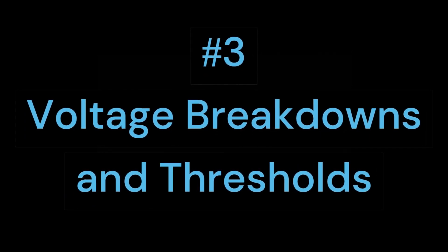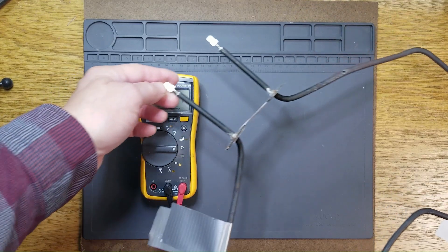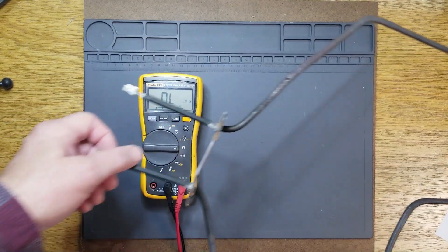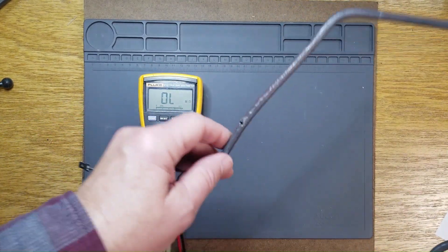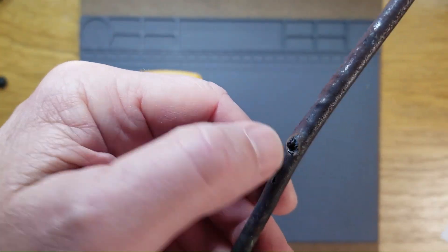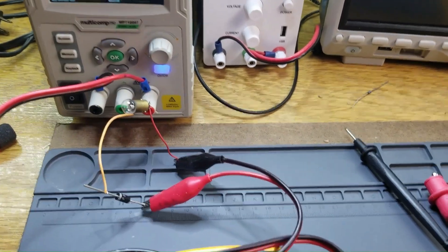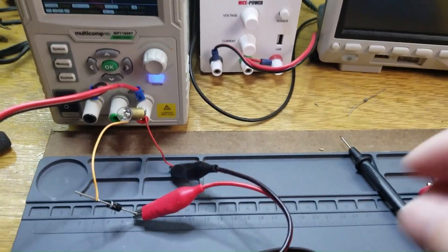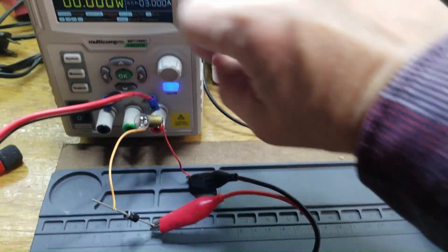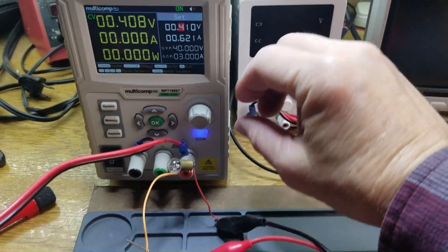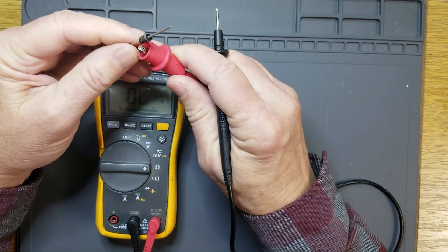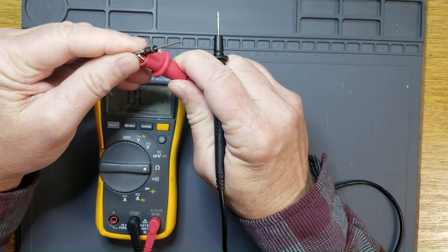Third is voltage breakdowns and thresholds, which will demonstrate how a bake element was tripping the breaker in a range but measured statically just fine when tested with an ohmmeter. And voltage thresholds, like with semiconductors, that readily pass current once they reach a certain voltage threshold, but when measured with your ohmmeter, they look like an open circuit.